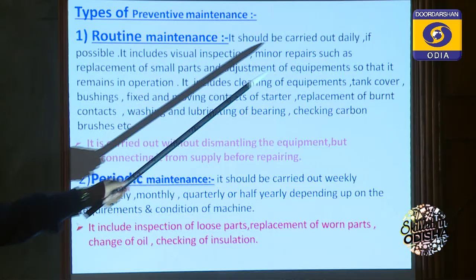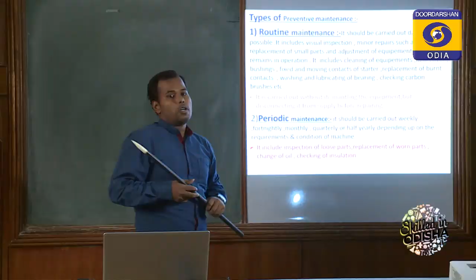Checking carbon brushes. Carbon brushes wear out, and we have to check on a daily basis. Only routine maintenance, you should note, should be carried out daily. A maintenance engineer keeps rounding in the plant and checks for these operations. Checking of carbon brushes, which wear out. He should check without dismantling. If any of these items written over here is found defective, then only he will dismantle it. Otherwise, he will not unnecessarily dismantle all of the apparatus to check it.